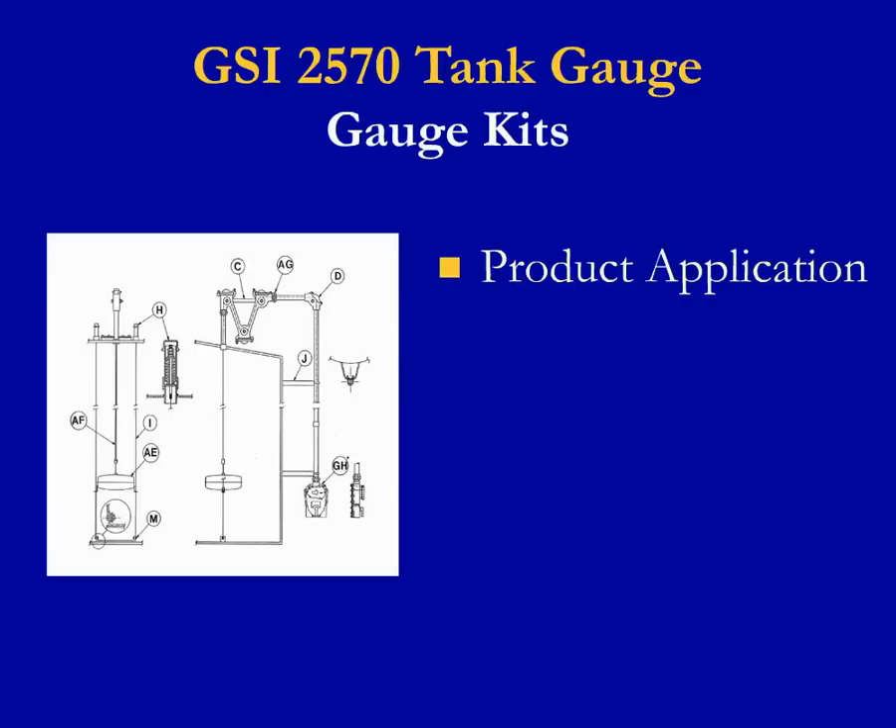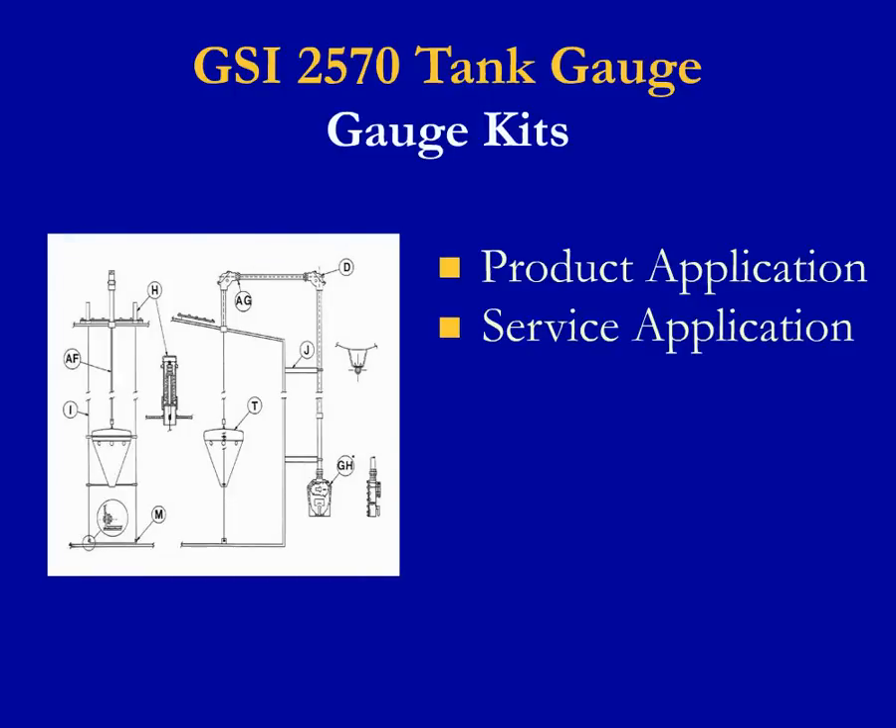As an example of a product application, we have developed a kit for asphalt where a liquid seal filled with kerosene is installed in the upper tape carrier pipe to keep vapors from entering the gauge head. This also serves a dual purpose as a cutting agent to clean the tape as it passes through the device. A special hollow shell stainless steel float with inverted float clips and a long swivel are used so that the clips are always immersed in the liquid product below the surface. A service application with success has been our turbulent and agitated product kit, where a cone dampener float fills with product and eliminates the float from bouncing to maintain level accuracy.